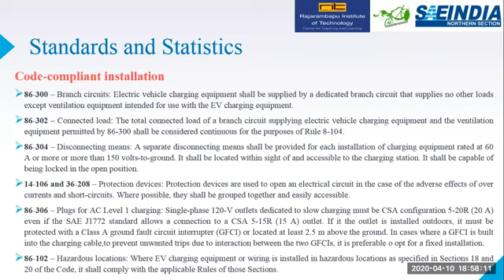Next, code compliant installation. This is a very lengthy document, which I have just added here for reference. There are 86, 300, 302, 304, 306, 102 norms. These norms, or advisories, are for people to follow if they want to establish a charging station for EV. The 300 norms cover the branch circuits or connected load, disconnecting means, protection devices, and plugs for AC level 1, level 2, and so on.